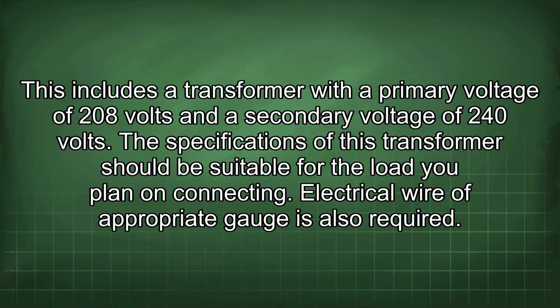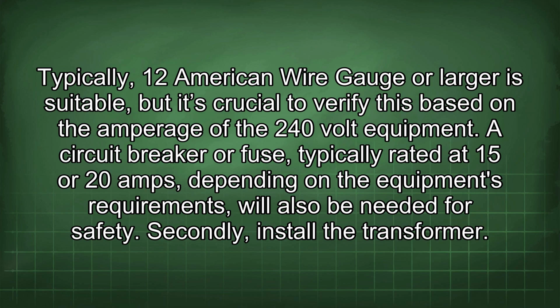Electrical wire of appropriate gauge is also required. Typically 12 American wire gauge or larger is suitable, but it's crucial to verify this based on the amperage of the 240-volt equipment. A circuit breaker or fuse, typically rated at 15 or 20 amps, depending on the equipment's requirements, will also be needed for safety.